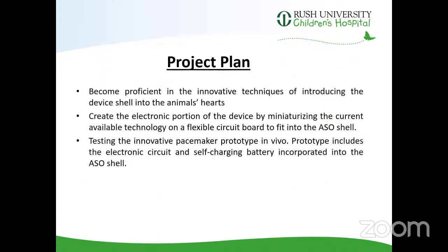And the project plan is summarized into three stages. The first one is for the team to become proficient in using the innovative techniques of introducing the device shell into the animal's heart. And the animal proposed was rabbits, white New Zealand rabbits. And at the same time, creation of the electronic portion of the device, including the battery, to mount it into the shell, which is either the ASO shell or other similar device.